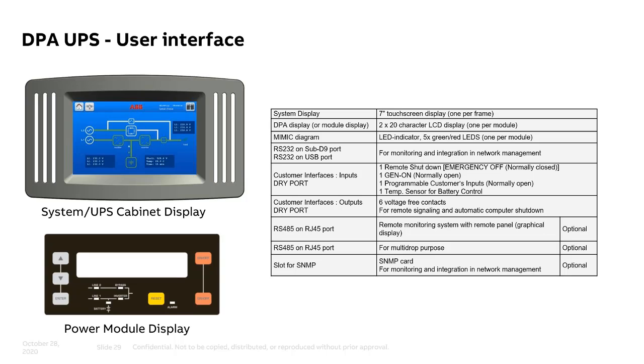But each 100 kW module in the modular UPS actually has its own display. The benefit is that if the one on the front of the UPS should go blank for whatever reason, and we are back to anything man-made will fail, it's just a question of time, I can open the door and go to any display on any power module in the system, and I can still operate the entire system. That little power module display, of course, doesn't look as fancy. It's not a color touchscreen. It doesn't have the same level of system data, but it can operate at a system level. So with the design, we added redundancy on the operation side as well.